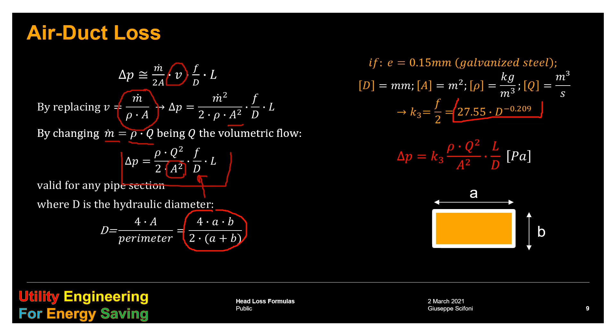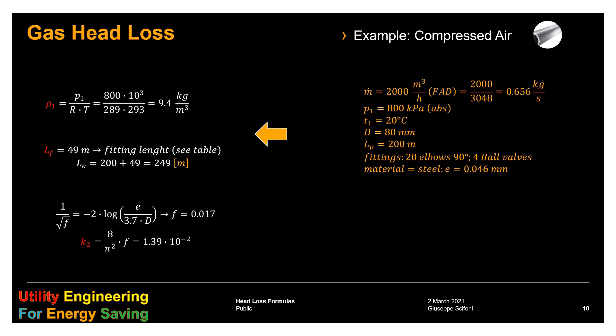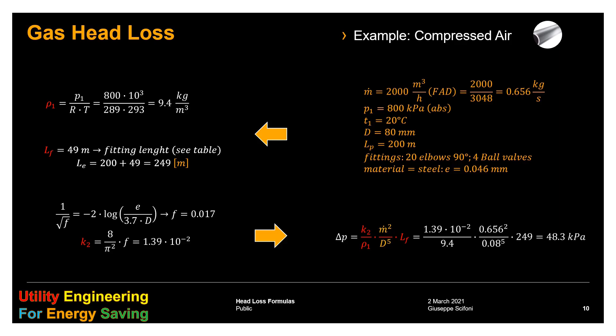The first is for compressed air. Known are the mass flow rate, the pressure and temperature, the diameter and the pipe length. At first, we calculate the density by the state equation, and we get 9.4 kg per cubic meter. Then we find the equivalent length, adding the contribution of the fittings. From the diameter and the pipe roughness, we calculate the friction factor F and the constant K2. That way we have all the ingredients to fill in the formula, and we get 48.3 kilopascal, almost half a bar.